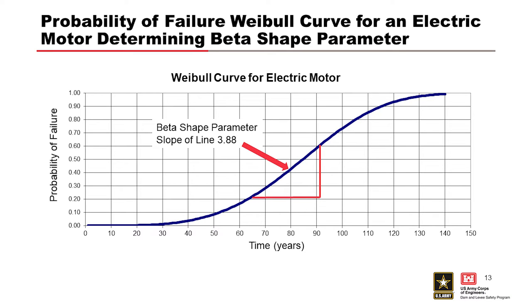Again, here's the Weibull curve for electric motor developed from data that we've collected at USACE projects. This particular one has a beta shape parameter of 3.88. The higher that number goes, the steeper the slope at that point, the quicker that your component will fail after it reaches the characteristic life.